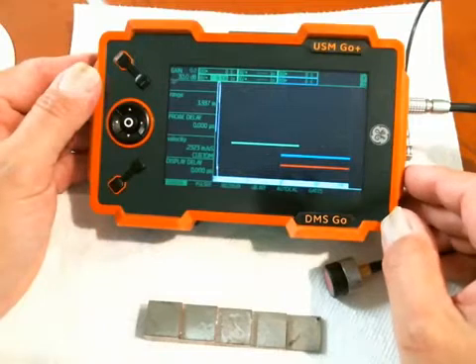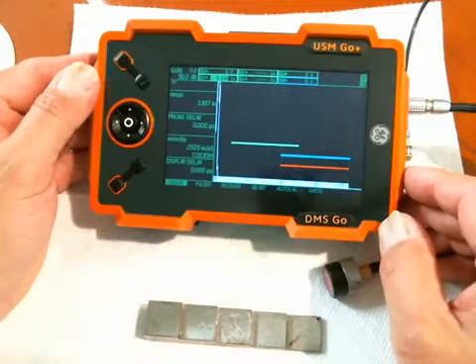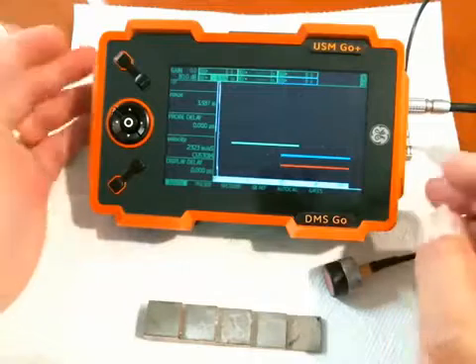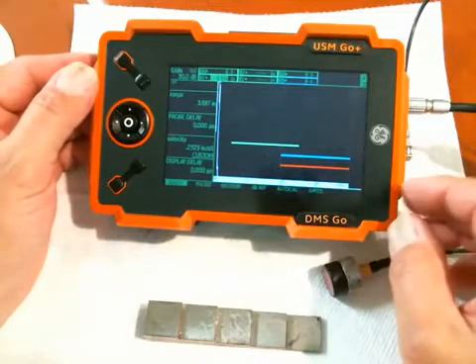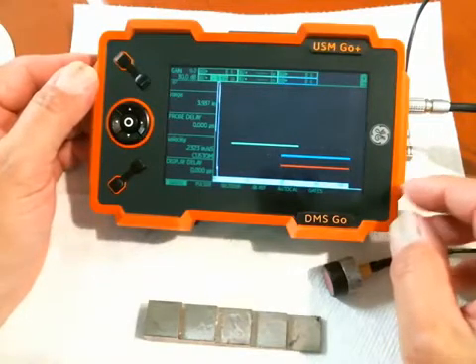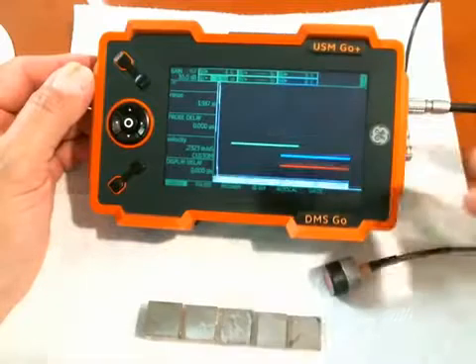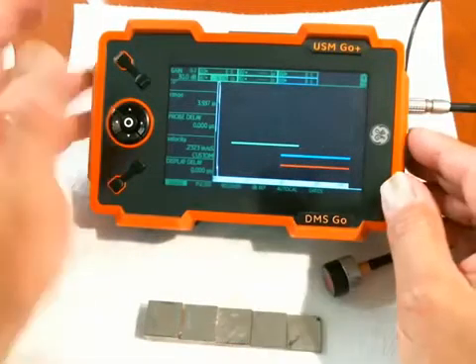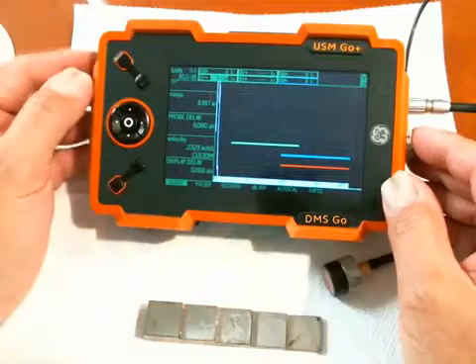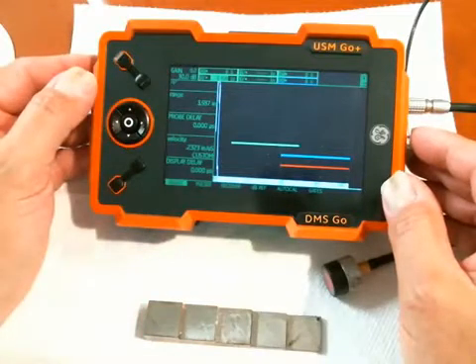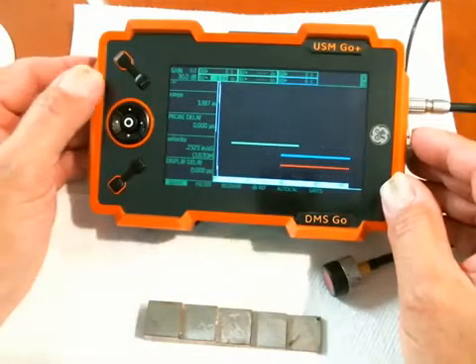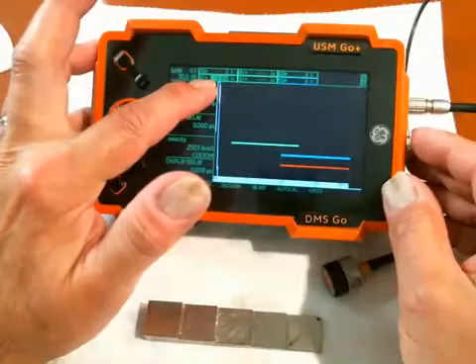A couple of things we want to set up. A thickness measurement is generally taken on the USM-GO flaw detector by measuring the sound path to an echo in one of the gates. In this case, we're going to use gate A. The readout for sound path in gate A is SA — sound path in A. It's already one of the selected readings in a small box.